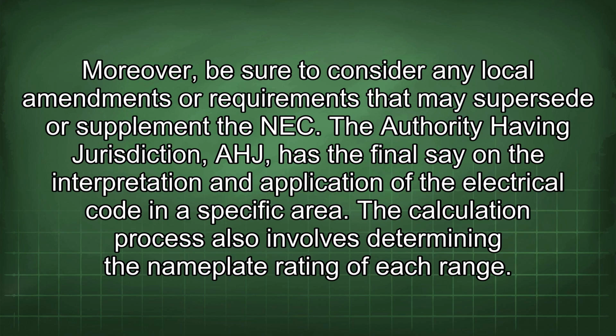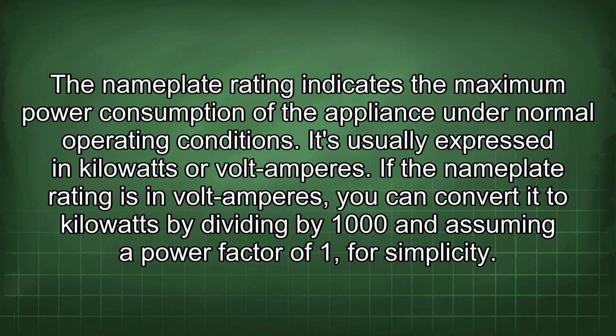The calculation process also involves determining the nameplate rating of each range. The nameplate rating indicates the maximum power consumption of the appliance under normal operating conditions. It's usually expressed in kilowatts or volt-amperes. If the nameplate rating is in volt-amperes, you can convert it to kilowatts by dividing by 1000 and assuming a power factor of 1 for simplicity.